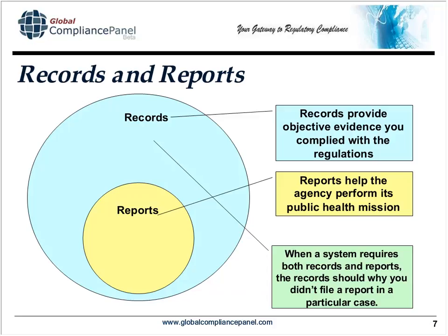Records and reports fit together in a particular way. Records provide the objective evidence that we've complied with the regulations. Reports help keep the agency informed to perform its public health mission. Reports are, in essence, some kinds of records — if you report something to the FDA, you're going to keep a record that you made that report. Sometimes the system requires both records and reports, but there are cases where you don't have to report, in which case you have to create a record explaining why you didn't have to report. We'll see that in corrections and removals: if you have one of the exemptions, you must keep specific records including the reasons why you didn't have to notify FDA.